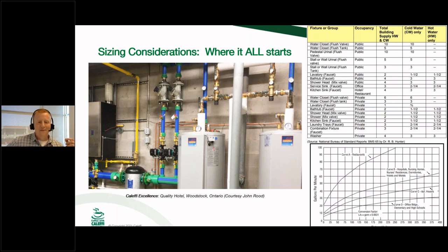Now, the first thing everybody wants to do is size it based on the maximum load, the maximum flow requirements of the system. So it's not typically so much a problem with residential applications, unless you start getting into those larger residential applications that might as well be commercial. But you get a commercial application, you're going to take account of all the fixtures. You're going to get all the fixture units. You're going to weigh them all out, and you're going to put that fixture count up against what is referred to as a Hunter's curve.